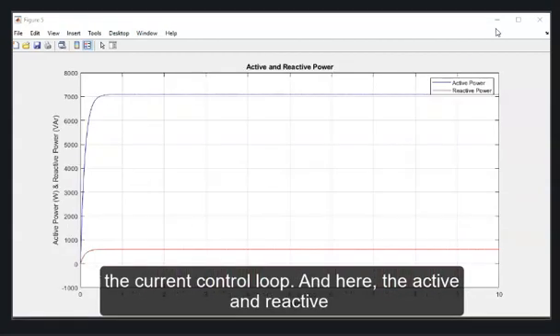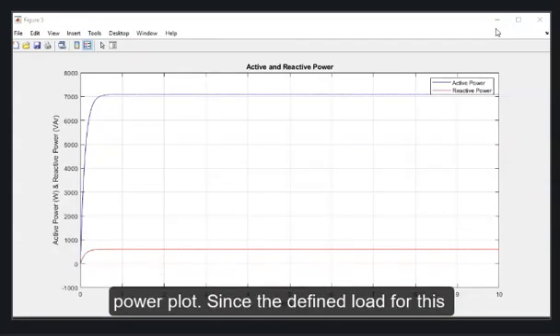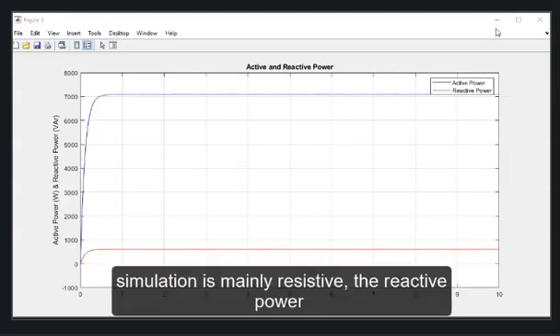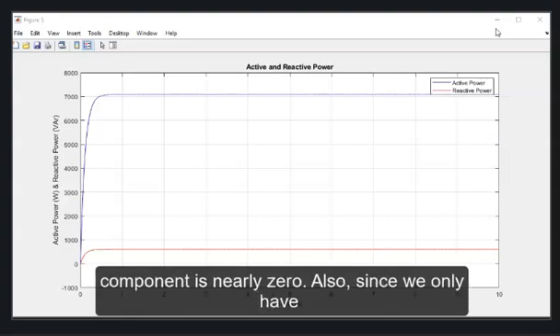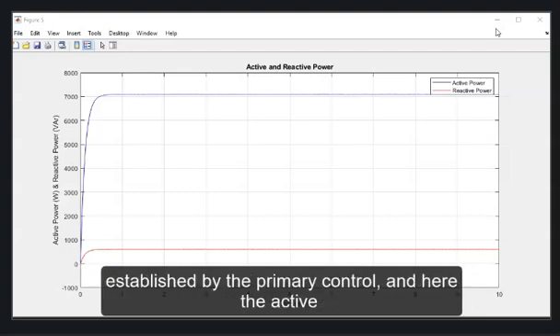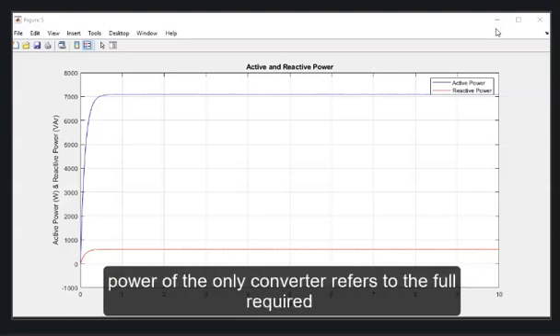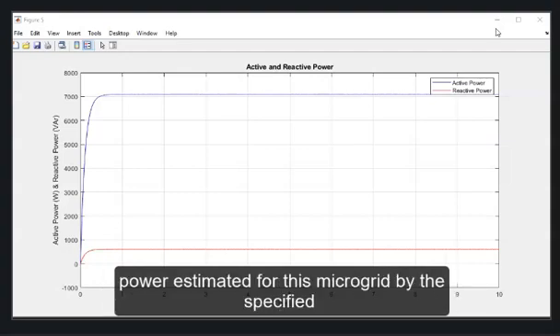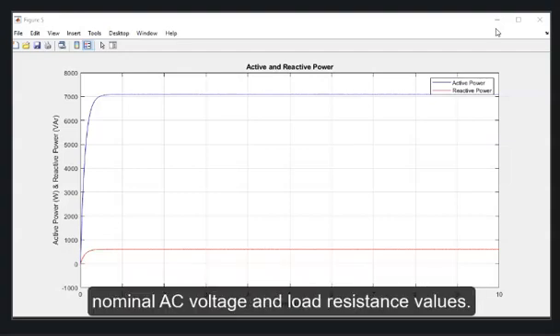And here, the active and reactive power plot. Since the defined load for the simulation is mainly resistive, the reactive power component is nearly zero. Also, since we only have one converter in this case, we cannot observe the power sharing established by the primary control. So, the active power of the only converter refers to the full required power estimated for this microgrid by the specified nominal AC voltage and load resistance values.